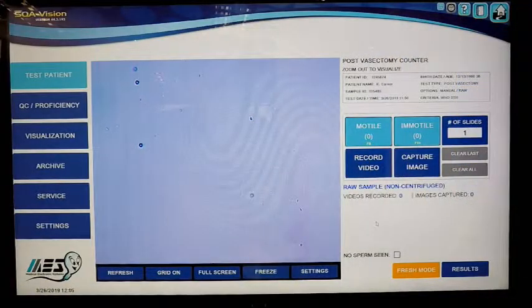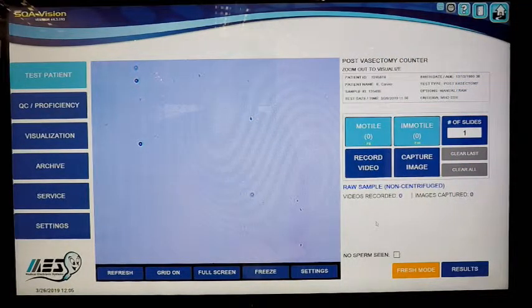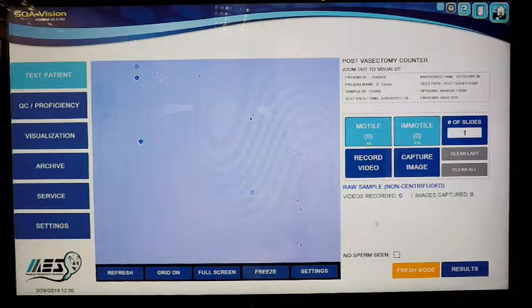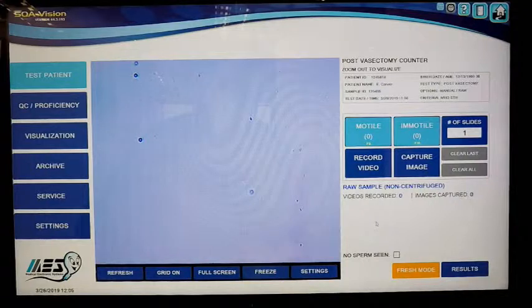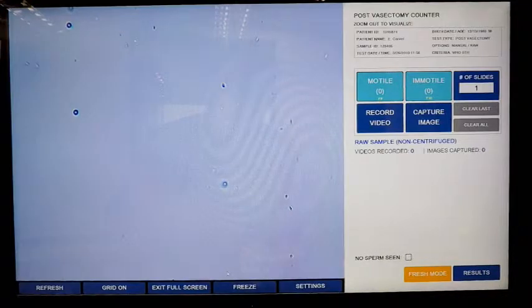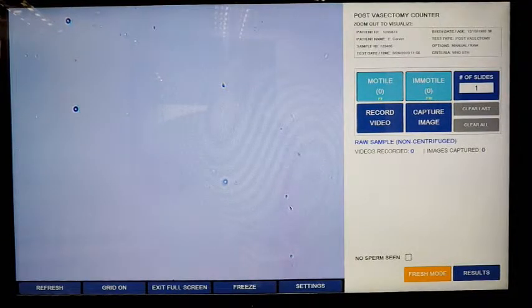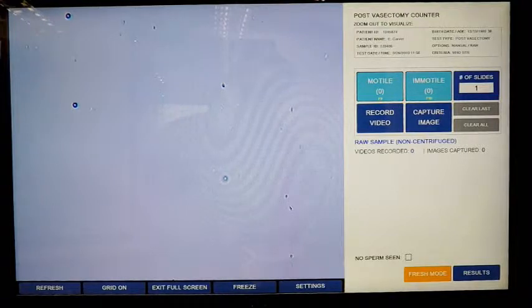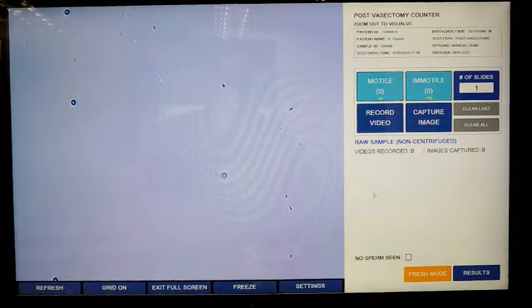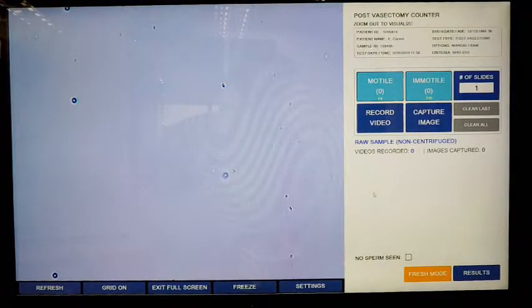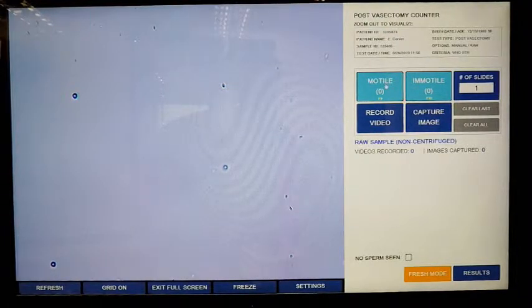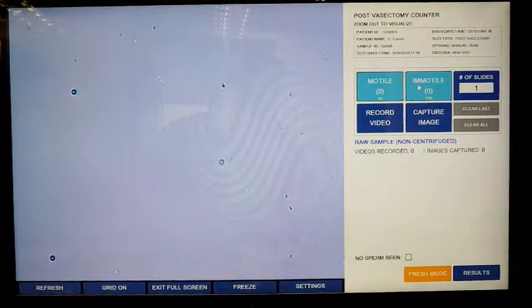I'm going to switch over to a view of the actual screen on the Vision. Back on the actual Vision app, we're looking at a digital image of the slide we inserted into the vision testing unit. You have the option to go full screen, which I always like to get a nice big view. You can see here I'm using quality control beads, but this is about the size of the head of the sperm as it will appear on the visualization system. The idea is we're just going to turn that adjustment knob from one lock point all the way to the other, which will give us 50 unique fields. As we go in real time, we're just going to select either motile or immotile as we see them visually on the screen.